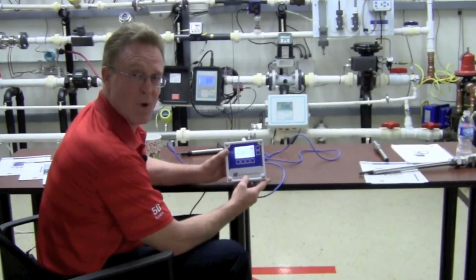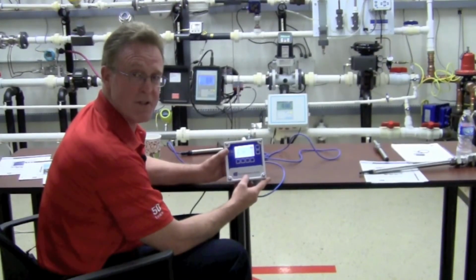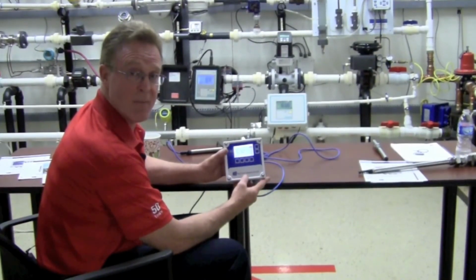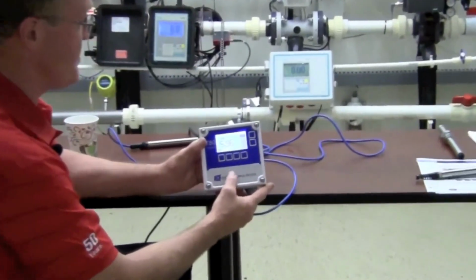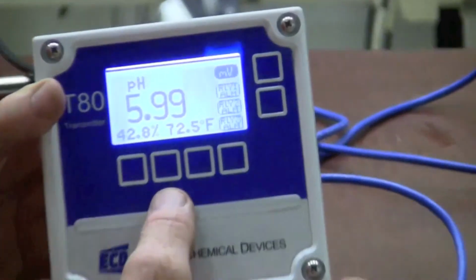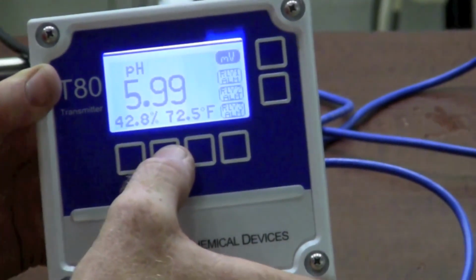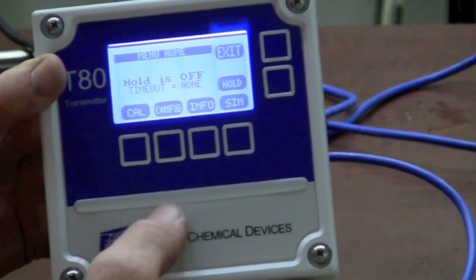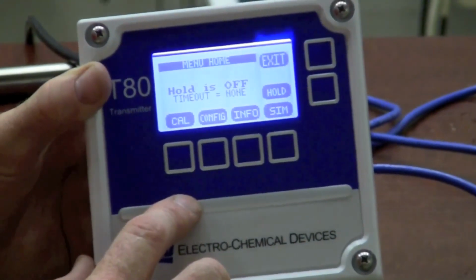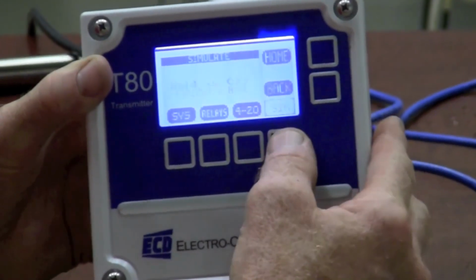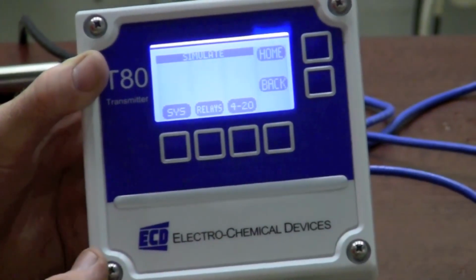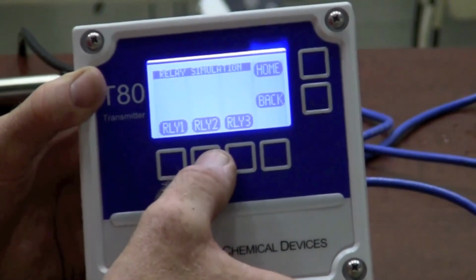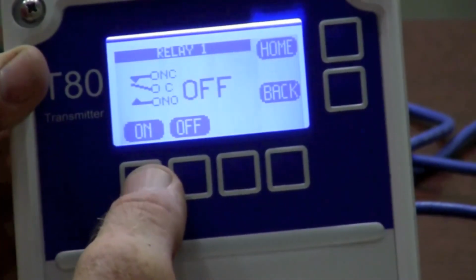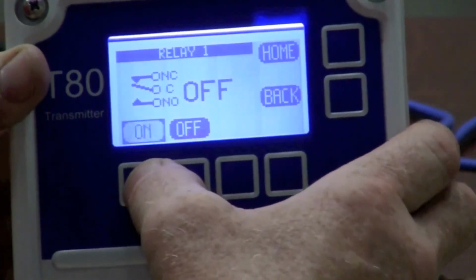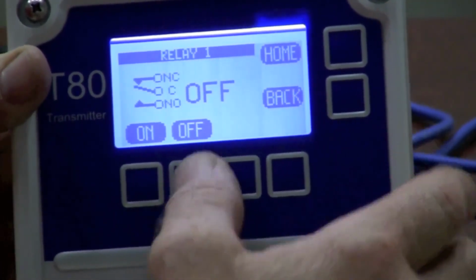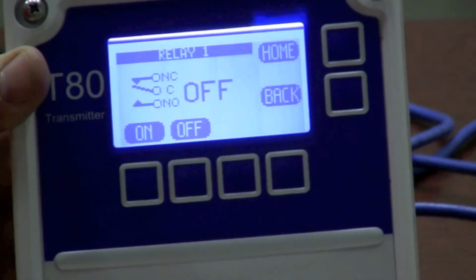Now that we've completed a calibration, I want to show you a couple nice features of the S80/T80 combo that make it a true winner. On the display, with the soft keys, once again I'm going to hit any one of the four twice in succession. And instead of going into the calibration, I'm going to go into the simulate. With simulate, this allows me to fire my relays if I wish. Relay 1, 2, or 3, and force it. This way I can ensure that my chemical feed is going to activate as I expect it to.